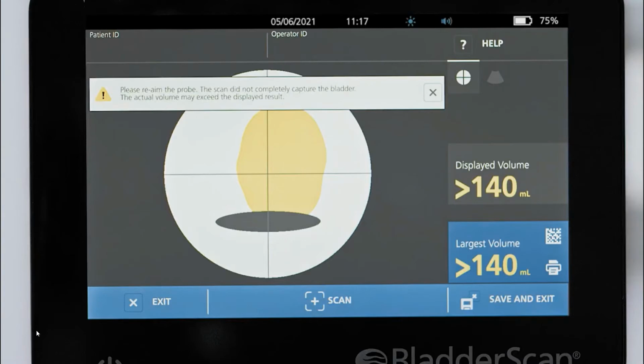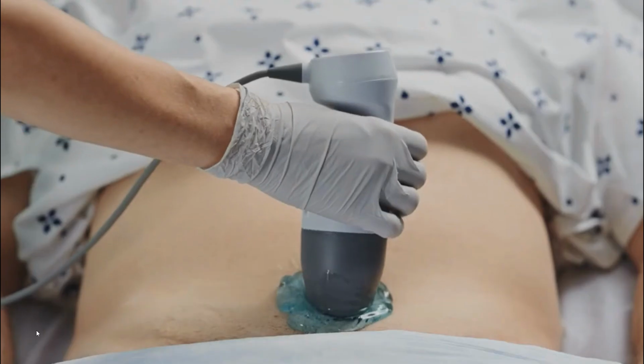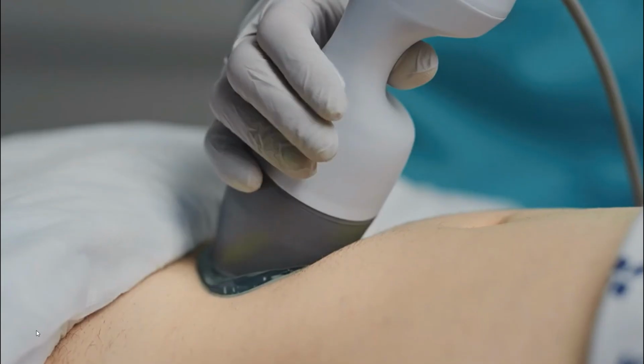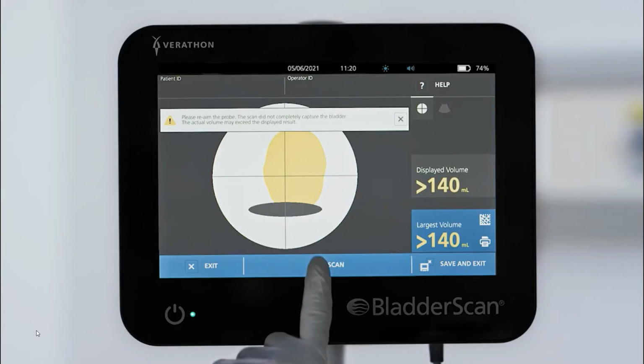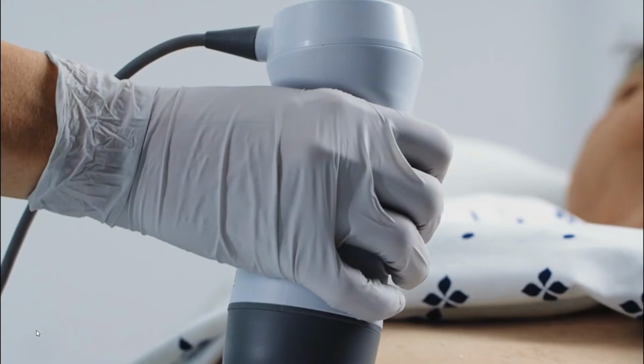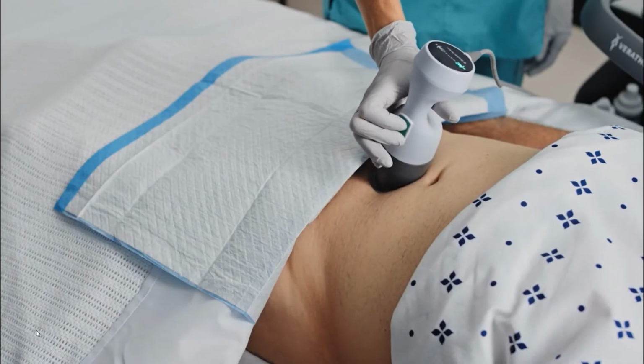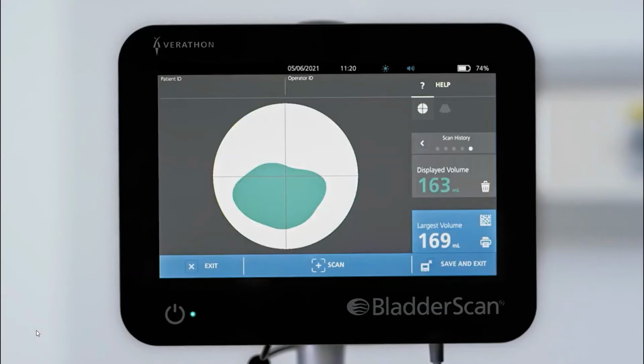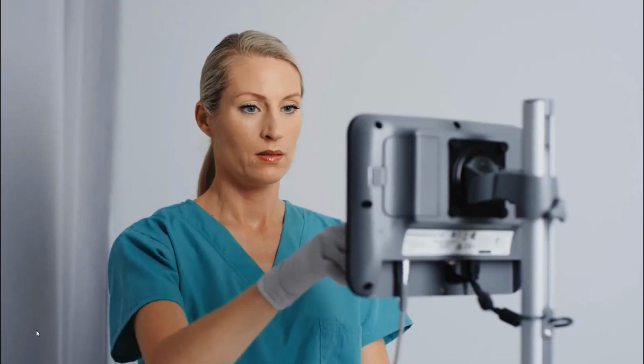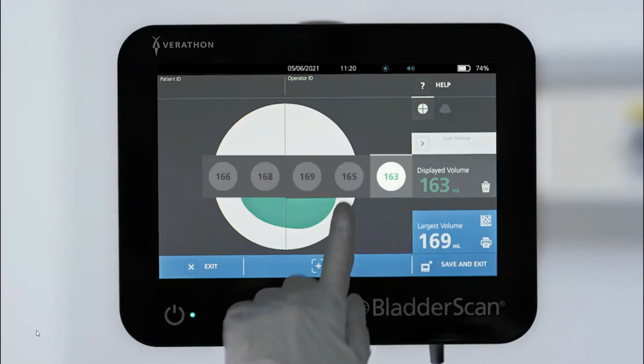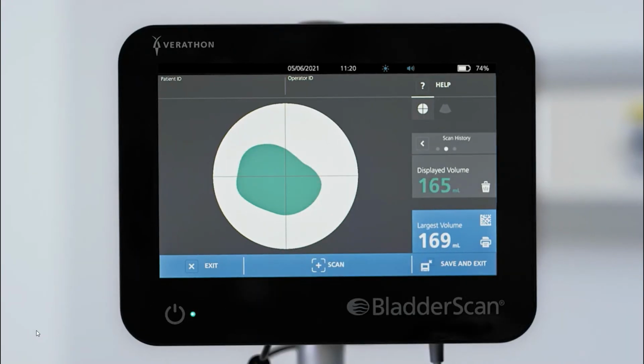If the bladder appears yellow and a greater than symbol appears, repeat the scan and make adjustments during aiming. Use appropriate probe angling and pressure. Press the probe button or tap the screen to scan again. When you perform a series of scans, the BladderScan system displays both the current volume and the largest volume measured in the series. Tap the scan history arrow to review any of the last 5 scans in the exam.